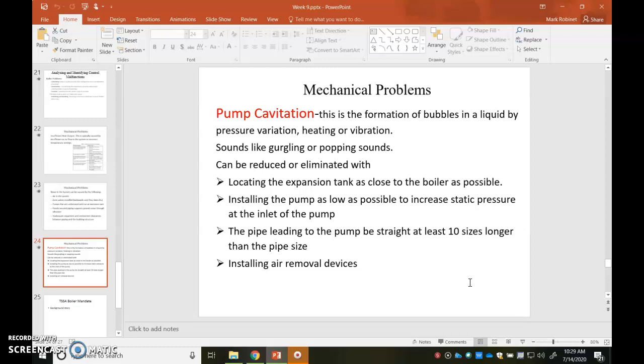Okay, so something easy. And then installing air removal devices would be another way that we can get rid of what we call pump cavitation. So again, pump cavitation is the pump creating kind of like water bubbles by trying to suck in some water or pump some water around that doesn't have a good flow of water.